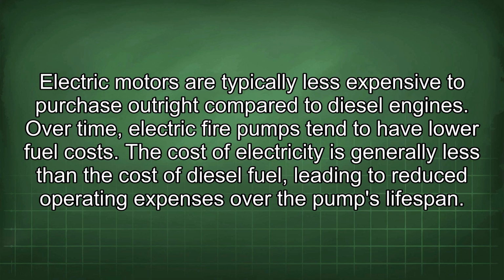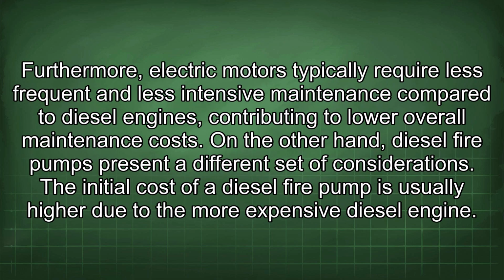Over time, electric fire pumps tend to have lower fuel costs. The cost of electricity is generally less than the cost of diesel fuel, leading to reduced operating expenses over the pump's lifespan. Furthermore, electric motors typically require less frequent and less intensive maintenance compared to diesel engines, contributing to lower overall maintenance costs. On the other hand, diesel fire pumps present a different set of considerations.